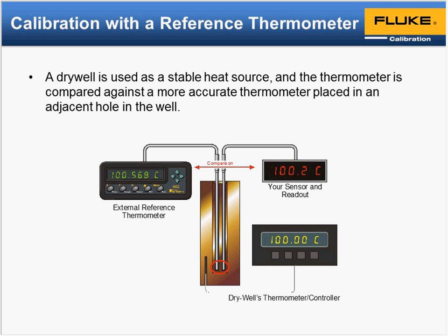In this example, we've set this up again. We've got the external reference thermometer in the well. We've got a unit under test in the well, immersed fully at the bottom. This gives you a break: maybe our dry well thinks it's 100, our UUT might think it is 100.2. In reality, we're seeing 100.568, which is what we would be calling true temperature for this particular calibration method.